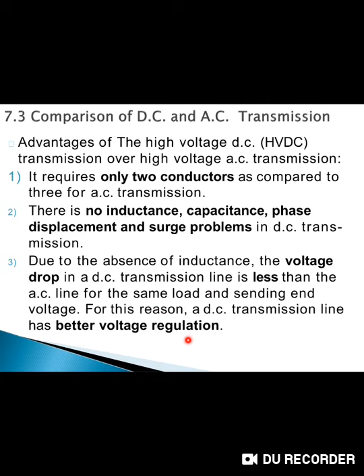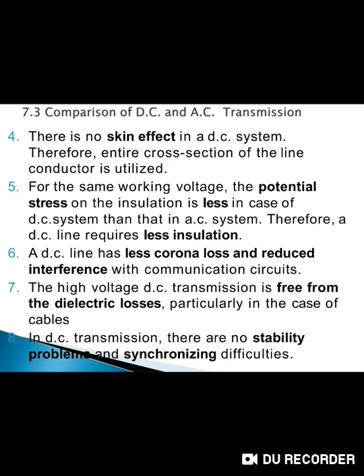Next, skin effect. The skin effect is only present in an AC system. There is no skin effect in an HVDC system. Again, next point, for the same working voltage, the potential stress on the insulation is less in a DC system when compared to an AC system. Therefore, a DC line requires less insulation. Sixth point, a DC line has less corona loss because there is no commutation problem. Seventh point, high voltage DC transmission is free from dielectric losses, particularly in the case of cables. In HVDC cables, there are no dielectric losses. Last point, in DC transmission, there are no stability problems.